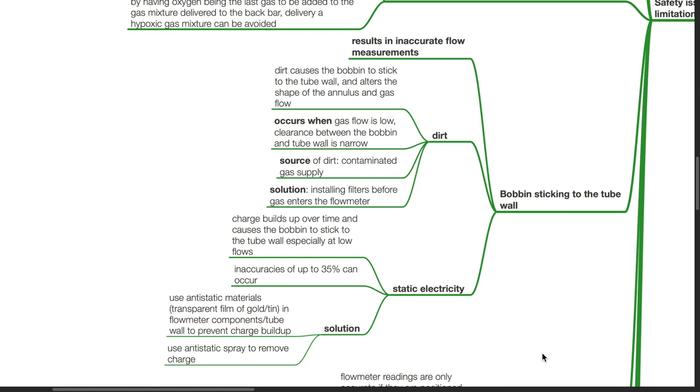Clearance between the bobbin and tube wall is narrow. The source of dirt is contaminated gas supply. Installing filters before gas enters the flow meter.